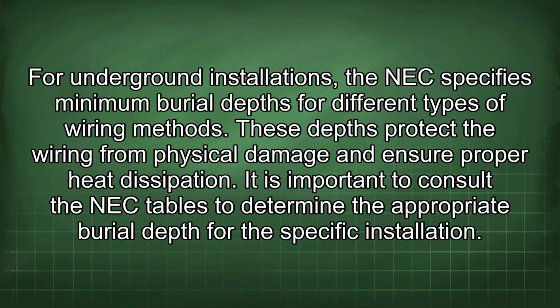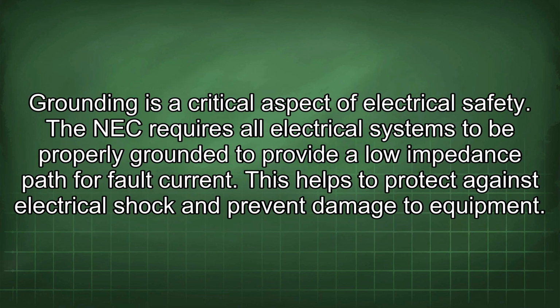For underground installations, the NEC specifies minimum burial depths for different types of wiring methods. These depths protect the wiring from physical damage and ensure proper heat dissipation. It is important to consult the NEC tables to determine the appropriate burial depth for the specific installation. Grounding is a critical aspect of electrical safety. The NEC requires all electrical systems to be properly grounded to provide a low impedance path for fault current. This helps to protect against electrical shock and prevent damage to equipment.